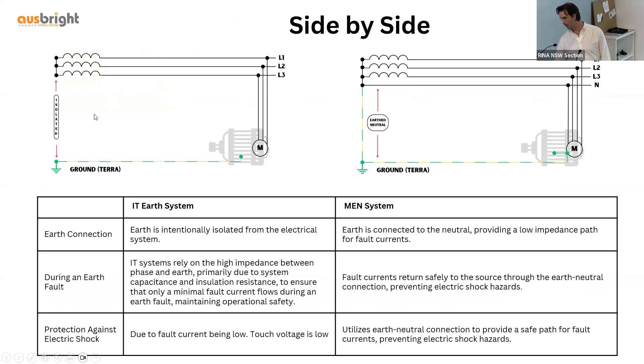Side by side, you can see isolated versus connected. IT systems during an Earth fault, because of the high impedance between the fault and ground, mean that the first Earth fault will result in very low current.